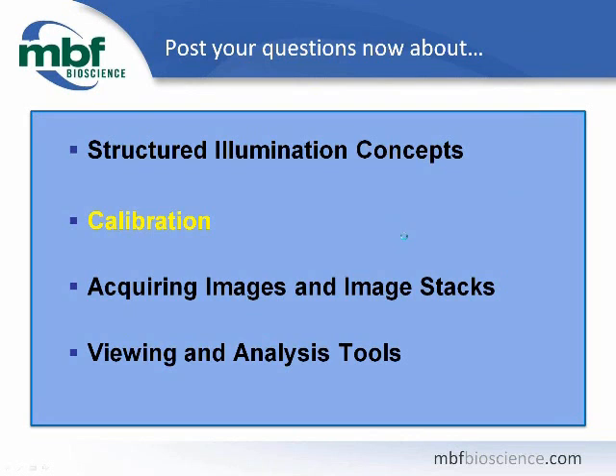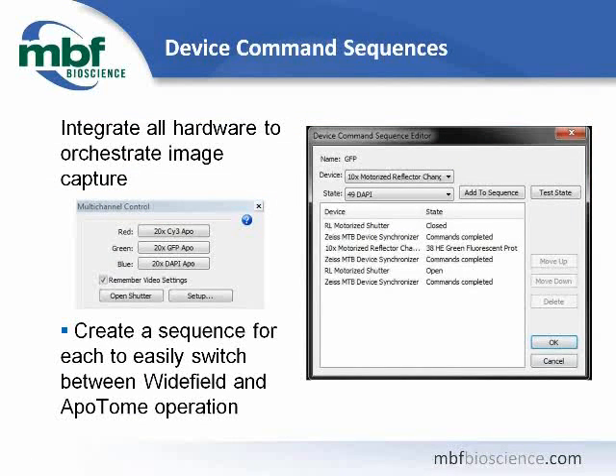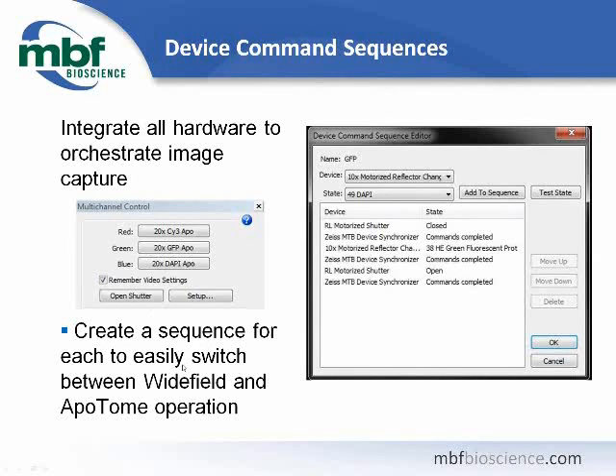Before we get started, we need to talk about device command sequences. Device command sequences integrate all the hardware together to orchestrate the image capture. In the multi-channel control window, each of the multi-channel acquires — in this case red, green, and blue — have an associated set of commands specified in the device command sequence editor. My naming convention indicates the objective, filter, and ApoTome so I can easily identify which filter combination to employ. Make sure the Remember Video Settings box is checked.